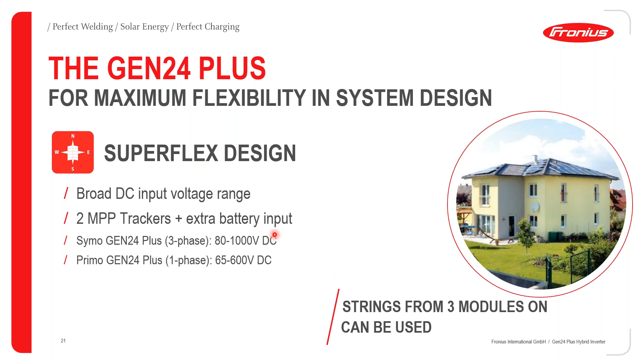In addition, we also have the Superflex capability or design in the Gen24 Plus inverter. And that means that, as I had mentioned before, all the Gen24 Plus inverters have 2 MPPTs built in. So that makes east-west design or south-west installation of PV arrays very possible. It could be symmetrical or asymmetrical, depending on the exact roof orientations that you encounter. And this Superflex design is also implemented with a broad DC input range. So we can see, for instance, for the Symo Gen24 Plus inverters, these are the three-phase inverters, you can start from 80 to 1000 volts DC. And for the Primo Gen24 Plus inverters, you can start from 65 volts to 600 volts DC. So that means that you can start your PV string with only 3 modules upwards, for each of the MPPTs.